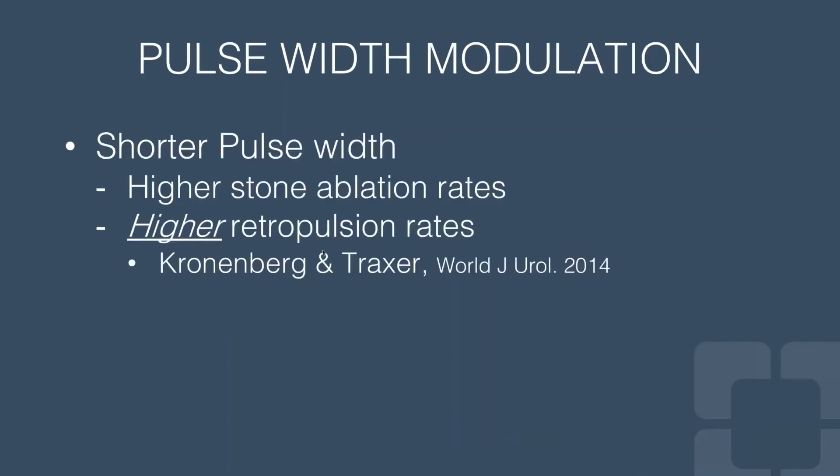Pulse width modulation has become a very integral factor in controlling stone breakage. Shorter pulse width is associated with higher stone ablation rates, as reproduced in multiple studies. Although the stone fragmentation rate is higher with shorter pulse width, the problem is higher retropulsion because the impact is much greater.